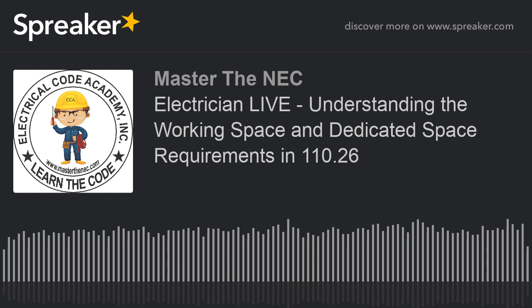It says, indoor installations shall comply with 110.26(E)(1)(a) through (E)(1)(d). So I've got an A, B, C, D that I have to comply with. Let's look at A, the dedicated electrical space. That's my space. That's your space as an electrician. I don't want no HVAC guy in my space. I don't want no plumbing guy in my space. This is my space. It is the footprint of this equipment.